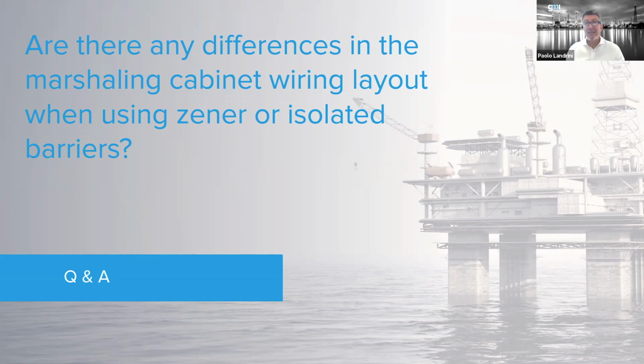Yeah, basically intrinsically safe means that it is safe, inherently safe. So when you use an IS solution, whatever you do in the field, you can short the wire, you can cut the wire, you can do whatever you want, and still the energy available will not be sufficient to ignite the gas mixture present. Of course, if you selected the right apparatus and the right associated apparatus for the gas group that you are working with, because it's a big difference between hydrogen and methane or propane.